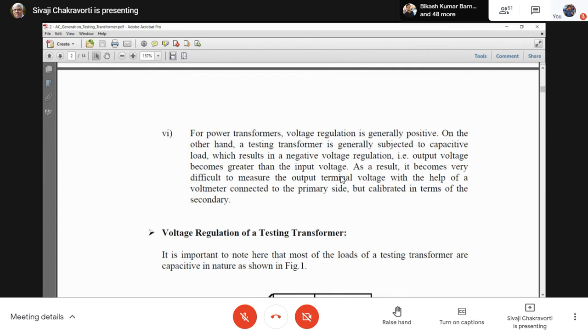Now, when I'm testing an equipment, as I said, I'm testing the insulation. So what is the type of load here, capacitive or inductive? Capacitive, because it's an insulation. So it is a capacitive load. That means the current that will flow is a capacitive current. And the transformer has its own impedance, which is inductive. Therefore, it's a case of capacitive current flowing through an inductive impedance. Exactly the case for voltage rise instead of a voltage drop.